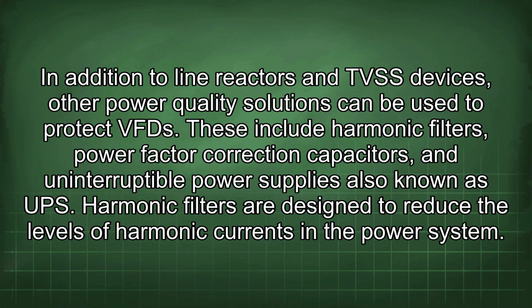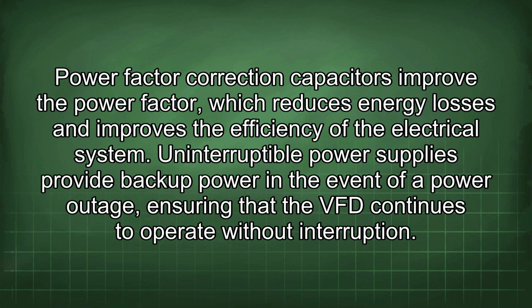In addition to line reactors and TVSS devices, other power quality solutions can be used to protect VFD. These include harmonic filters, power factor correction capacitors, and uninterruptible power supplies, also known as UPS. Harmonic filters are designed to reduce the levels of harmonic currents in the power system. Power factor correction capacitors improve the power factor, which reduces energy losses and improves the efficiency of the electrical system.